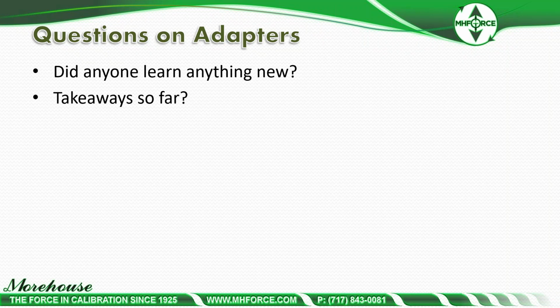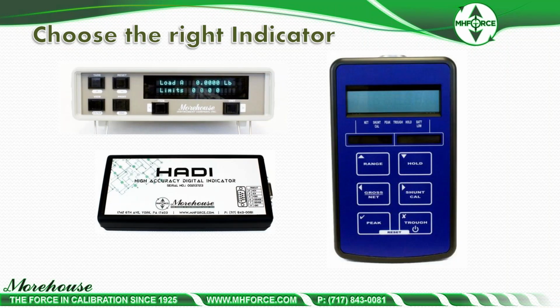And some takeaways. If you're doing truck scales, what's your takeaway? Are you going to go back and make sure you're standardizing, that you're using the right adapters? You're not stacking just a pad on it, because it's going to make a difference. The data there clearly shows that you're going to have an error if you're using X size and the customer's using Y size and they don't match. All bets are off.